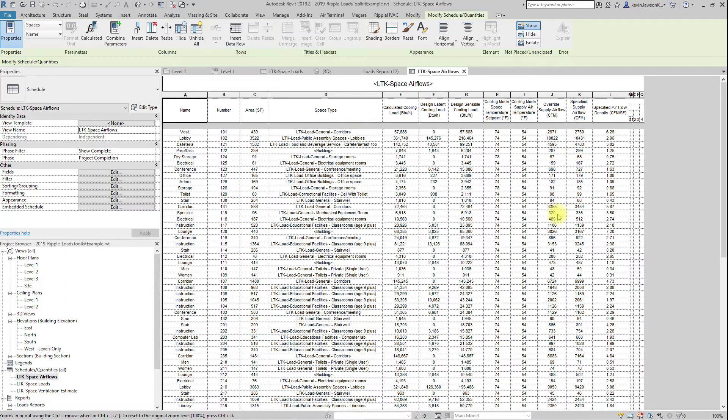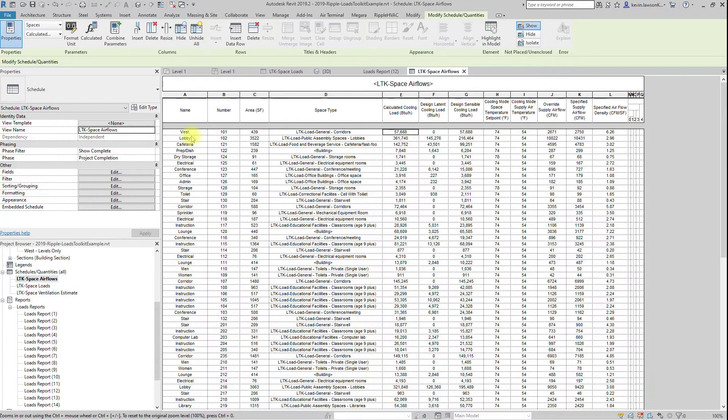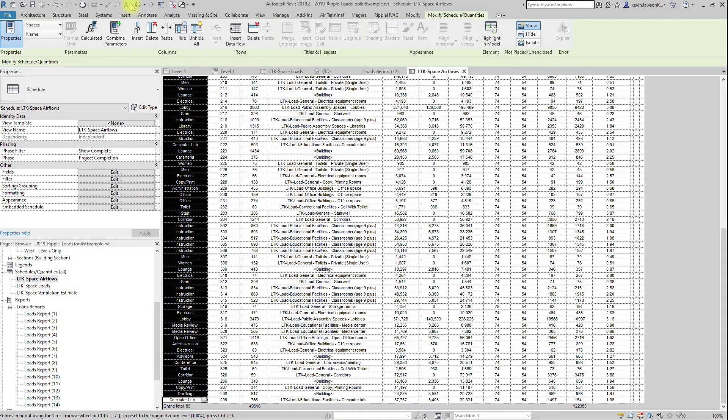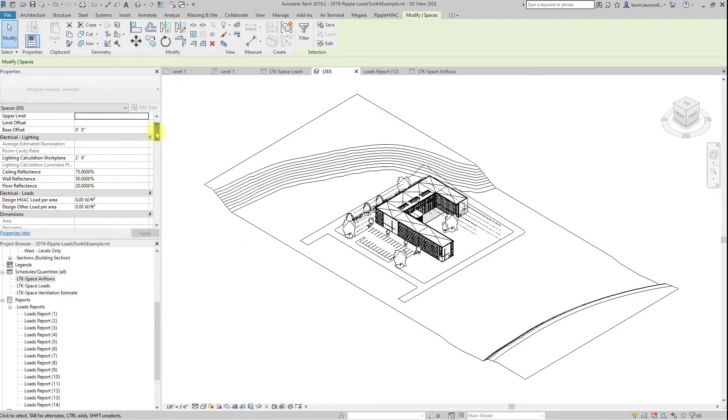You can look at the LTK space airflow schedule to calculate an accurate CFM. Modify your cooling mode supply air temperature parameter as necessary.